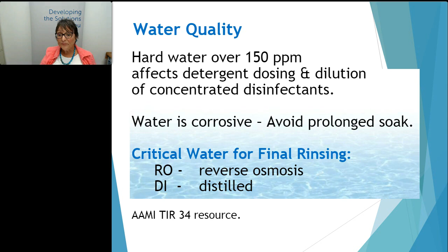And then I would like to send out an endorsement for the use of better quality water for rinsing. Even if your water quality is pretty decent and you don't have super hard water, they have found real benefits from ADA research with using DI water for the final rinse. So this is something I think would be good to discuss and check out in your office and with your particular water quality. The use of DI water is not too difficult in dental practices because we tend to have smaller devices. If you have automatic washers in your dental practice, you may have to consult with the washer manufacturer to figure out if there are some systems that you can use to improve the water quality going into your automatic equipment. And there is an AAMI document. This is not an ST79, this is a separate document, a technical report that is exclusively devoted to water quality, and that is available from AAMI.